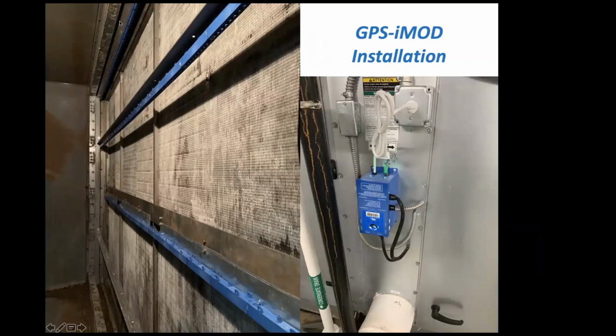Here we have an example of how it's installed in a larger air handler. You see a bar at the top, one on the middle coil, one on the bottom coil. We generally recommend 1 bar per coil up to 5 feet in coil height. Over 5 feet in coil height, we go to 2 bars.